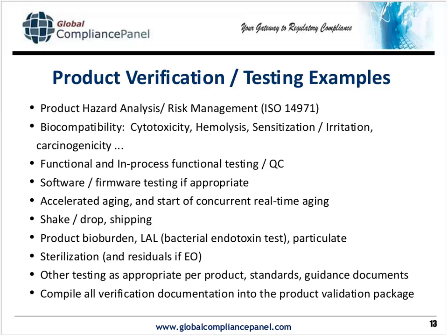Accelerated aging. Now, if you're filing a 510K, you will not have the real-time aging, but you will have accelerated aging data to show that you can at least theoretically, based on standard test procedures, meet the shelf life requirements that you put on your expiration dating. But then the FDA expects you to verify that accelerated aging by means of real-time aging studies.